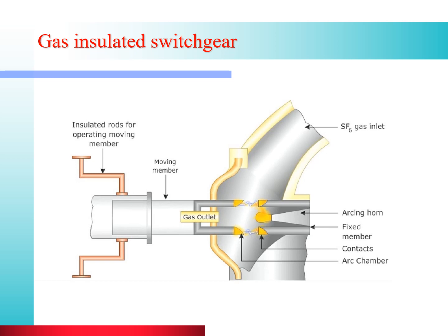Similarly, in the gas insulated switchgear, SF6 gas is generally utilized. This is the gas outlet, SF6 gas inlet, and after cooling, this gas will go through this outlet to the SF6 reservoir again, where it is recycled and reutilized. So this diagram shows the parts of gas insulated switchgear - every switchgear is insulated with the help of gas.